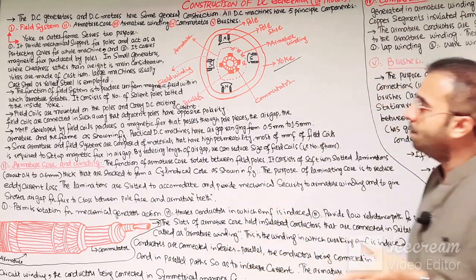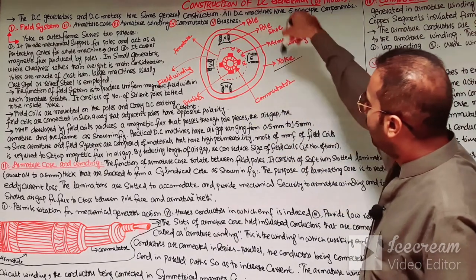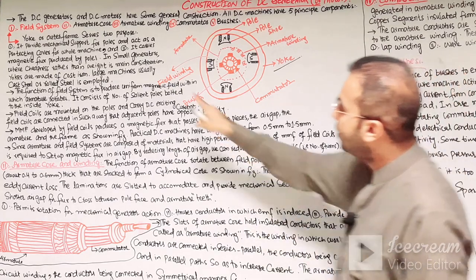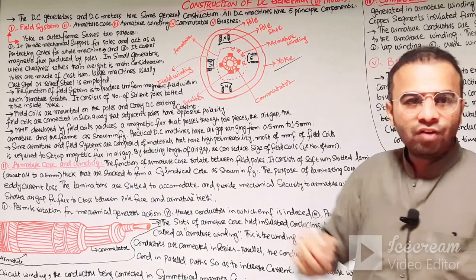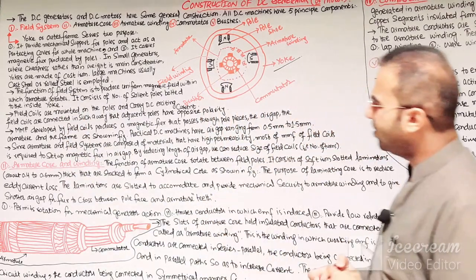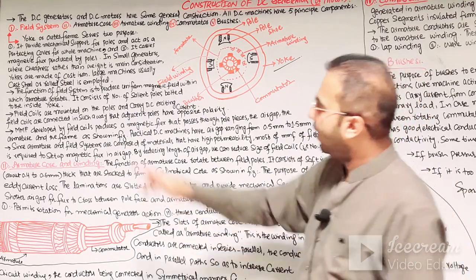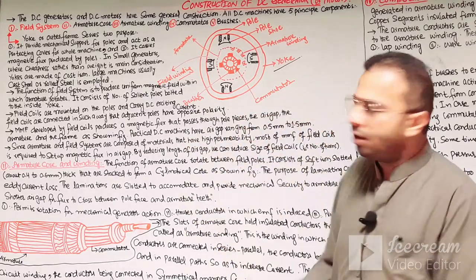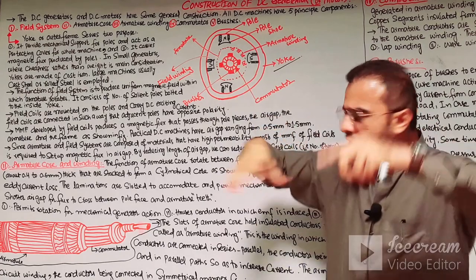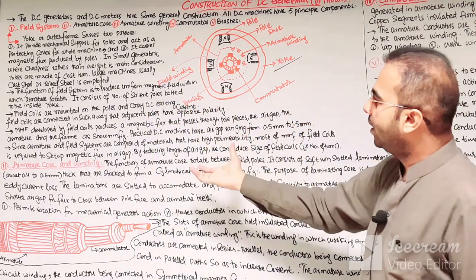In small generators where cheapness is a consideration, cast iron is used for making the yoke. But in the case of large machines, the yoke is made of cast steel or rolled steel. The function of the field system is to provide a uniform magnetic field when the armature rotates. It consists of a number of salient poles bolted inside the yoke, and the poles are fixed inside the cover or yoke of the machine.